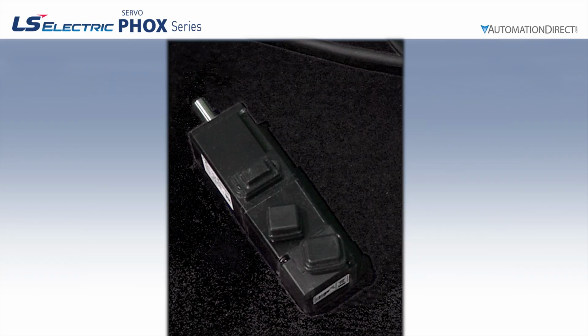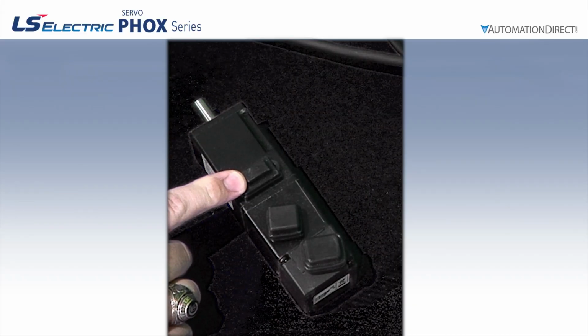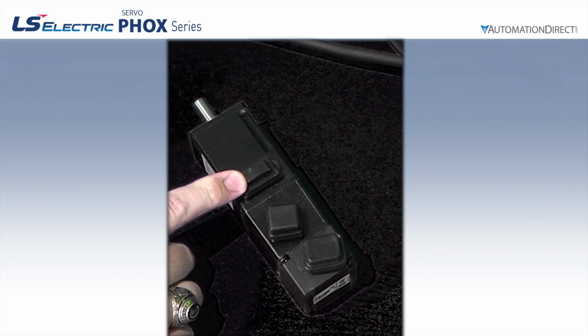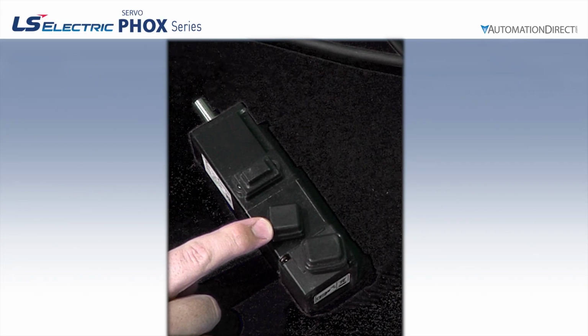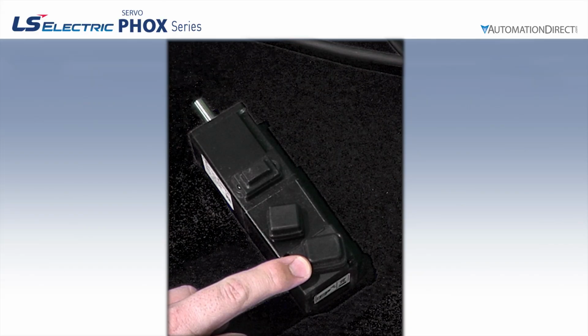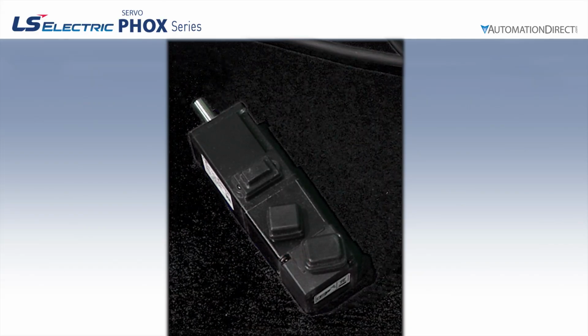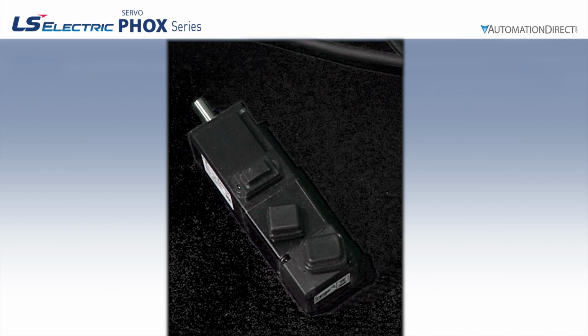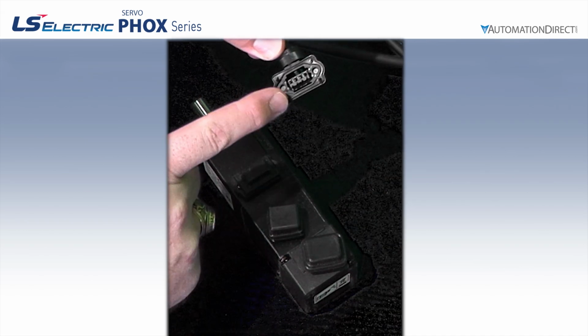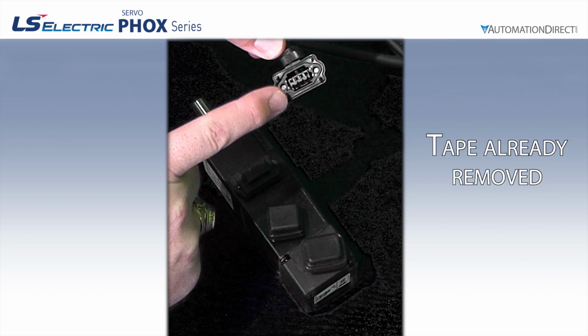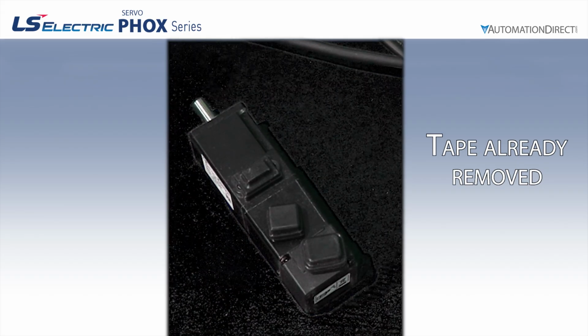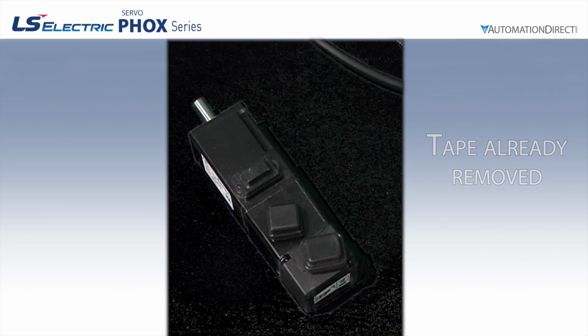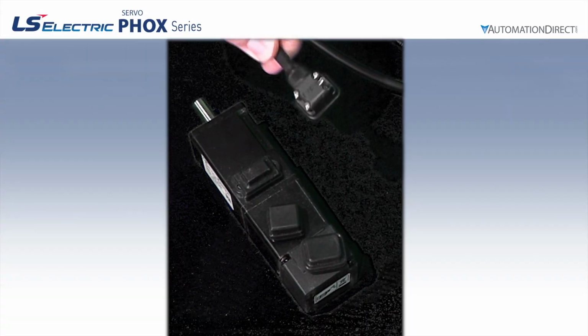As we begin wiring the motor, note that there are 3 connectors. The connector closest to the shaft is the motor power connector, followed by the brake connector if you have one, and then the encoder connector. All 3 come protected from the factory with small rubber boots. The cables for each connector may have a small piece of clear tape protecting the pinouts and securing the O-ring seals during shipping as well. Be sure and remove that if present. Let's wire the power cable first.